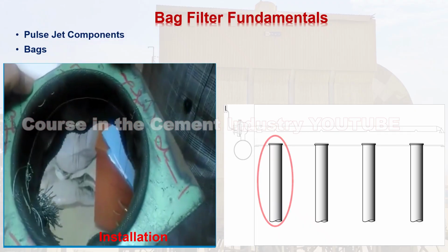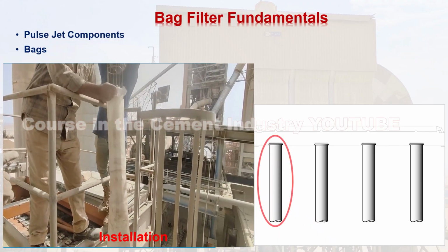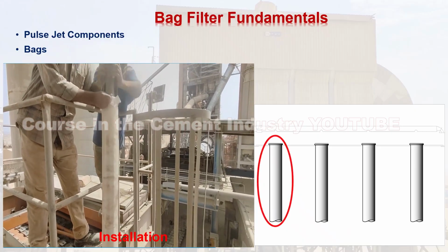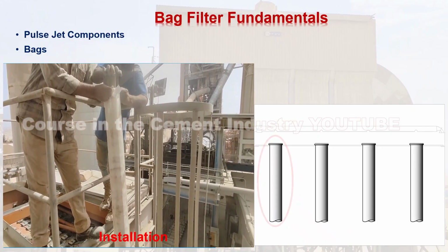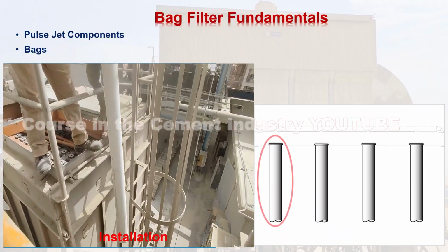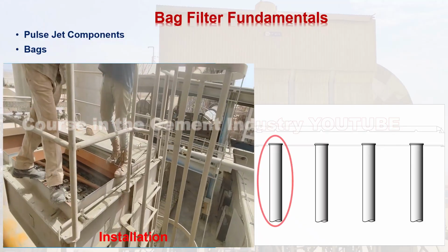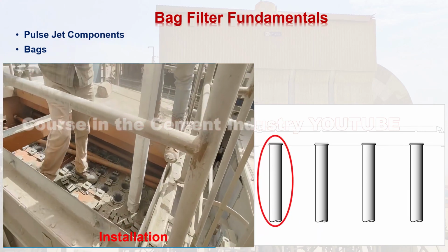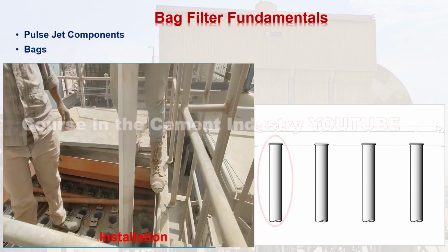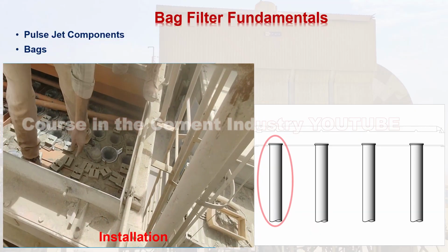The type of fabric, filter media. Following are some considerations you may need to keep in mind when choosing the suitable filter fabric, filter media, for your applications. 1. Air permeability of the material, fabric weight per square meter. 2. Fabric's finish and surface treatments or membranes. 3. Bag configurations: top, bottom, diameter, length, and sewing threads.